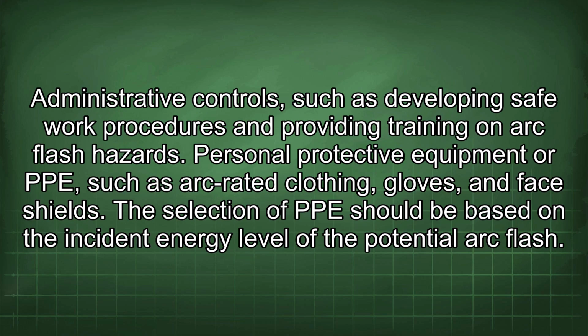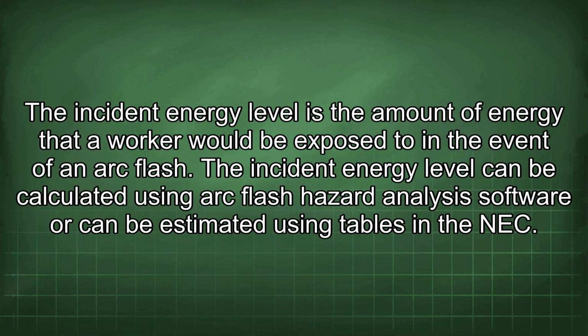The selection of PPE should be based on the incident energy level of the potential arc flash. The incident energy level is the amount of energy that a worker would be exposed to in the event of an arc flash. The incident energy level can be calculated using arc flash hazard analysis software or can be estimated using tables in the NEC.